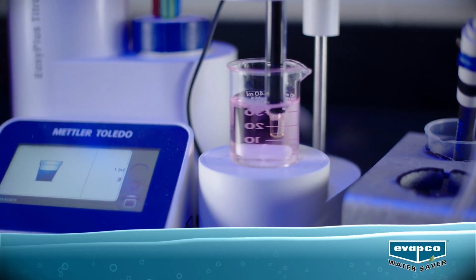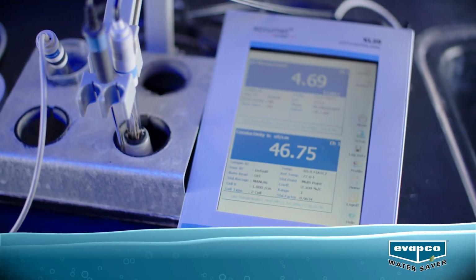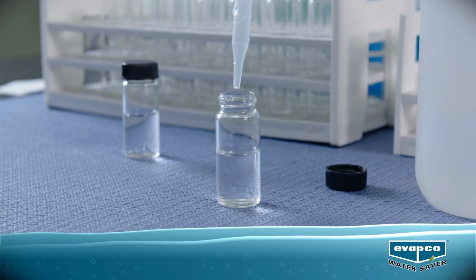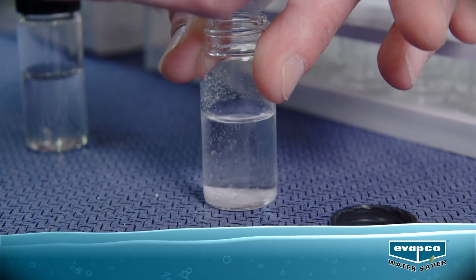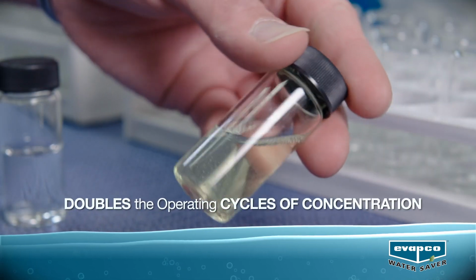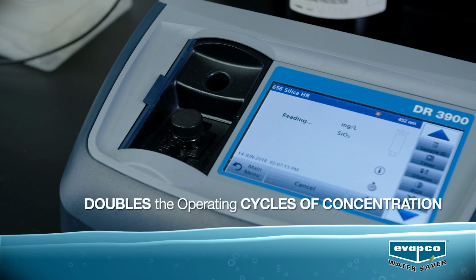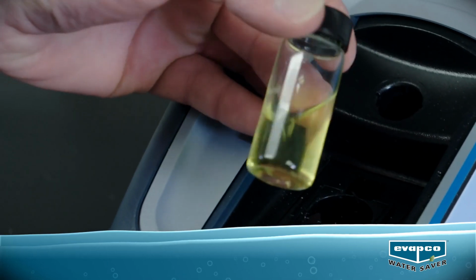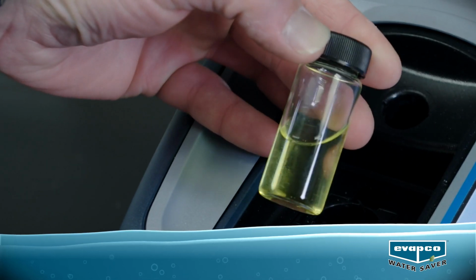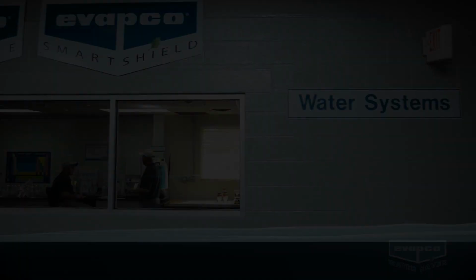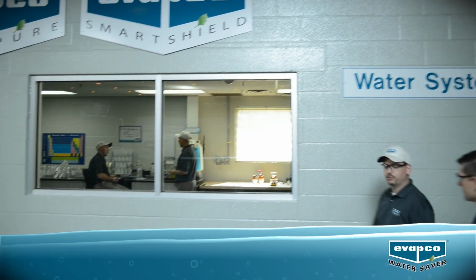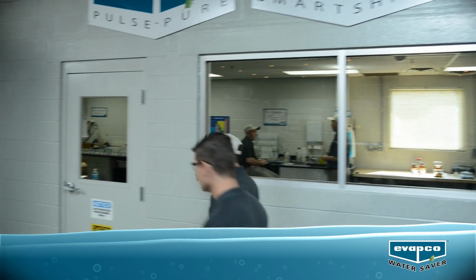The technology is applicable across a broad range of makeup water quality. In most cases, adding a water saver allows customers to safely double their operating cycles of concentration. The exception to this rule of thumb is water with high silica content. Otherwise, our capacitive deionization system has the ability to provide substantial water savings for the majority of cooling systems. EVAPCO continues to be the leader in water-saving designs developed in our extensive water analytical laboratories.